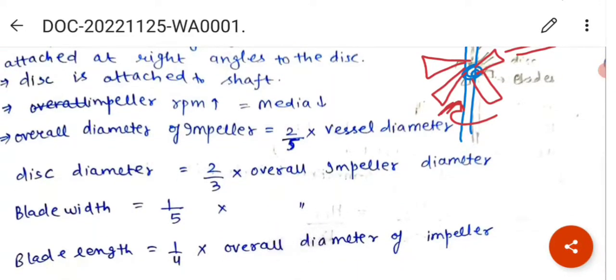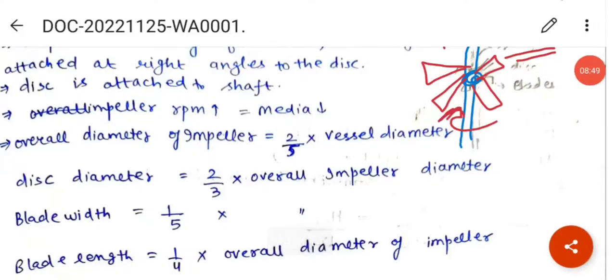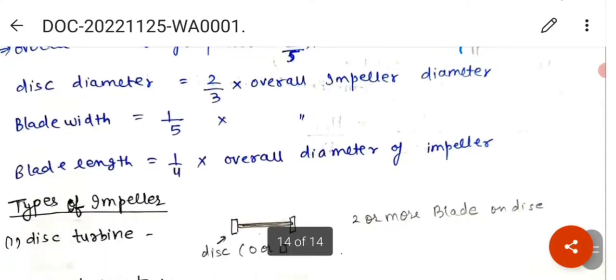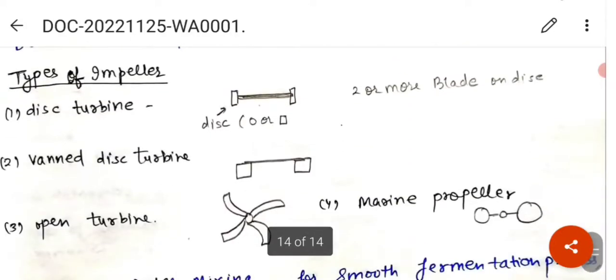The impeller RPM is revolution per minute. For impeller RPM high, medium is low. The impeller diameter is equal to 2 by 5th of the vessel diameter. Disc diameter is equal to 2 by 3rd of the overall impeller diameter. Blade width is equal to 1 by 5th of the overall impeller diameter. Blade length is equal to 1 by 4th of the overall diameter of the impeller.